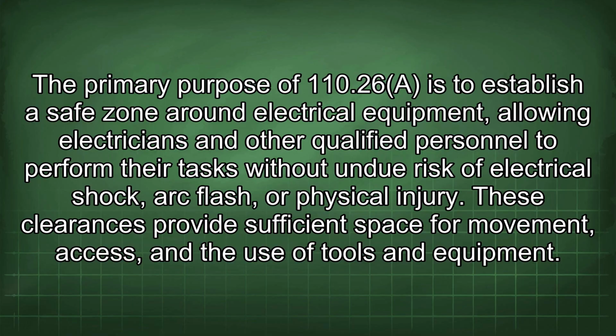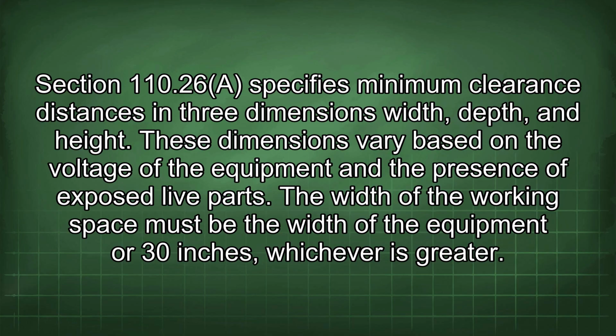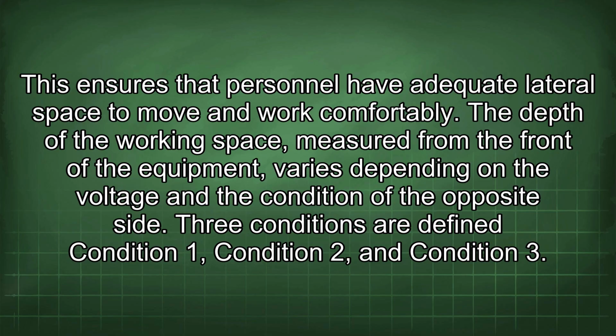These clearances provide sufficient space for movement, access, and the use of tools and equipment. Section 110.26 specifies minimum clearance distances in 3 dimensions: width, depth, and height. These dimensions vary based on the voltage of the equipment and the presence of exposed live parts. The width of the working space must be the width of the equipment, or 30 inches, whichever is greater. This ensures that personnel have adequate lateral space to move and work comfortably.